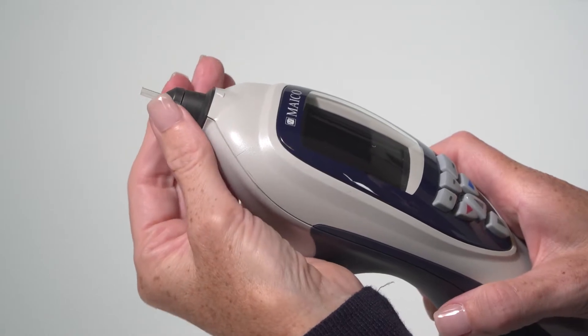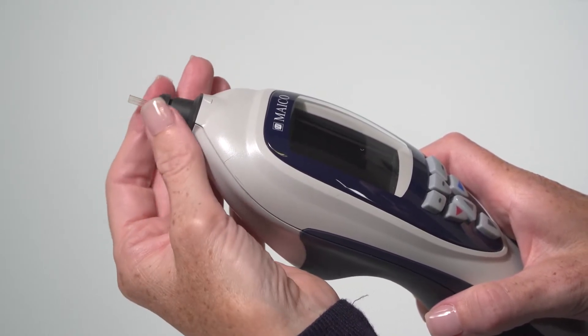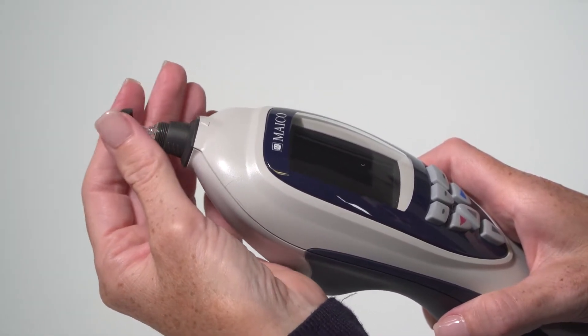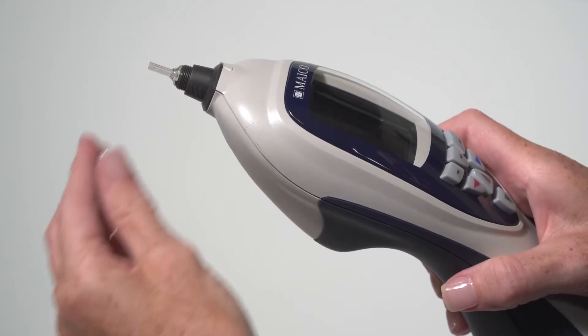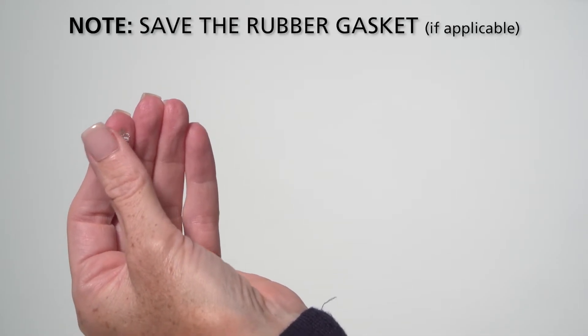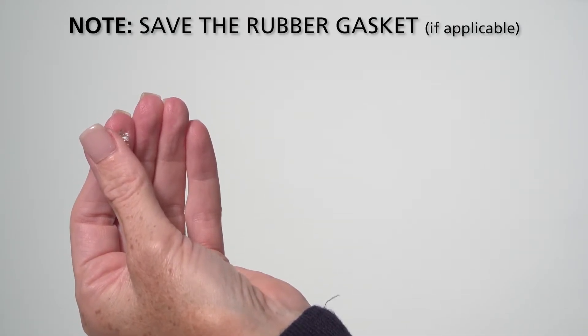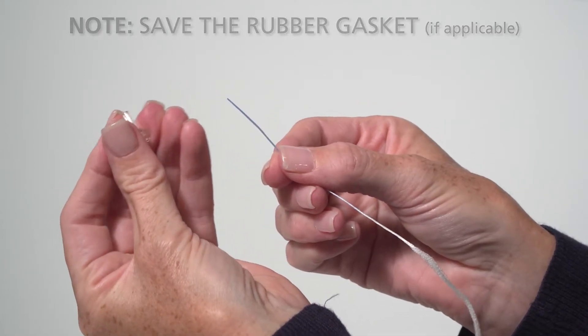To clean the probe tube, start by turning the probe cap in a counterclockwise direction. Never clean the probe tube while still attached to the probe. Take the plastic probe tube out of the probe. Depending on the tympanometer used, there may be a rubber gasket. Do not discard this rubber piece as it must be in place when cleaning is completed.